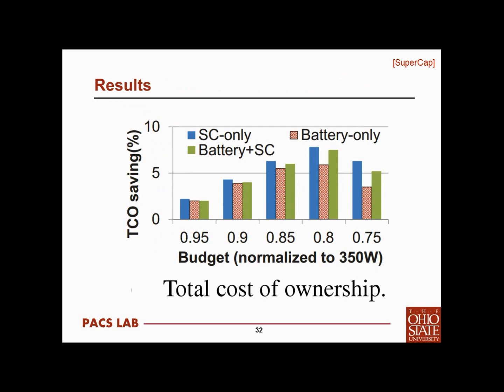We evaluate our system in a self-developed simulator. We evaluate the total cost of ownership, including the building cost of the facility and the cooling and the power infrastructure. We evaluate different construction options, including the supercapacitor-only case, the battery-only case, and the supercapacitor plus battery case. In our evaluation, we find that using supercapacitor only will give us the most total cost saving in our studied cases.